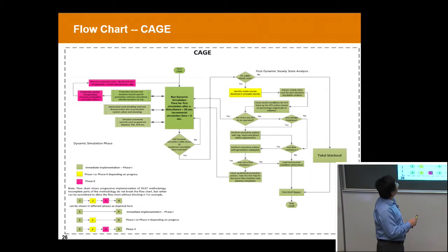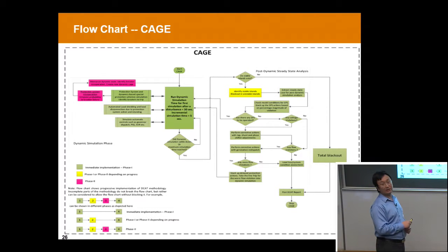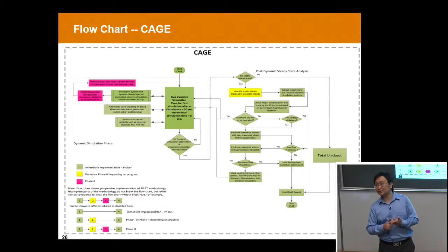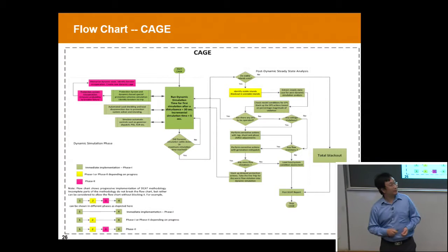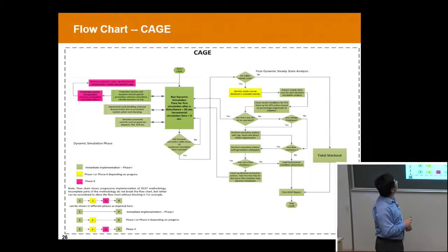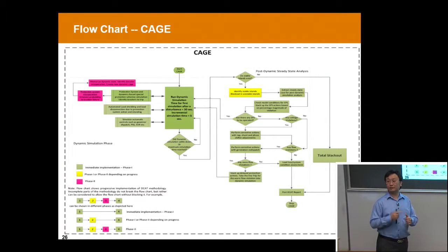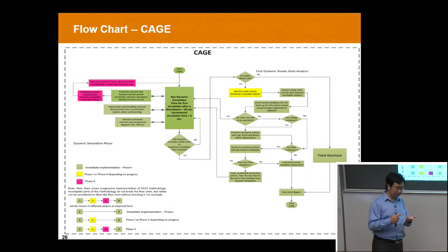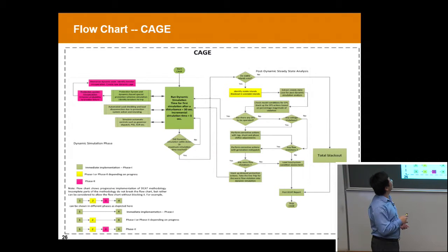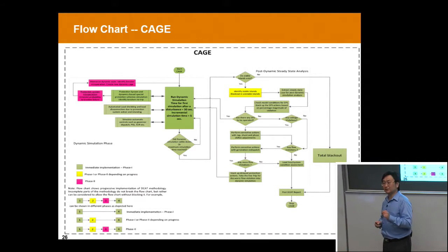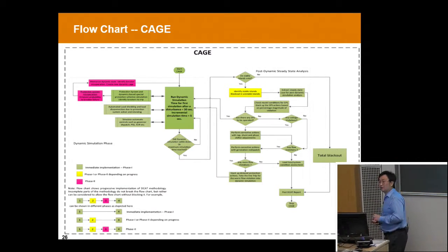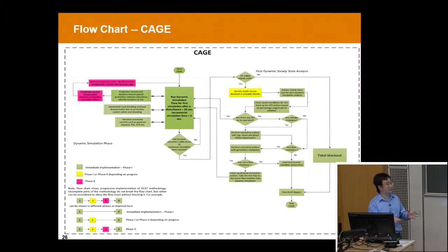On the left-hand side, we launch a dynamic simulation by properly modeling all necessary pieces, including traditional generator controllers—exciters, governors, PSS—and also protection relays for generators, loads, and transmission lines. We also need to include other specifically designed SPS or RAS actions into the model to generate good system performance.